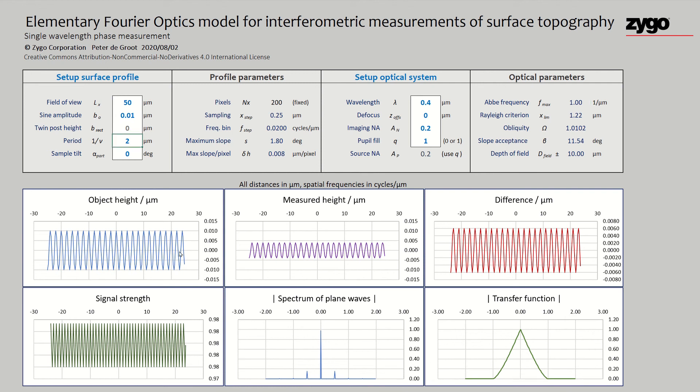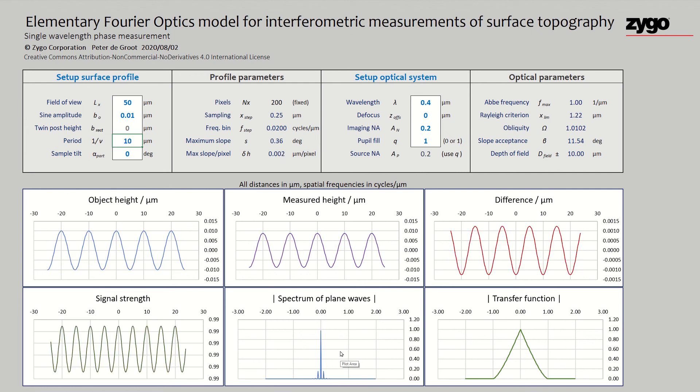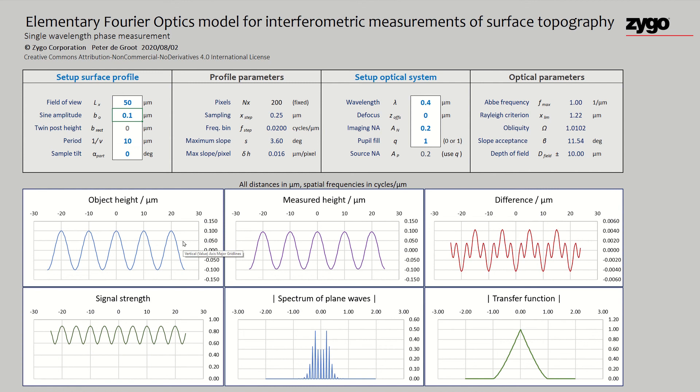If we change this period to 1, then we now have gotten to the edge and we don't see anything. So that's well understood. Let's go back to our original signal with the measured height now looking good. Let's change the amplitude instead of the period. We've changed now to 100 nanometers. At 100 nanometers, we've got a good strong measurement result. It looks almost identical to the original, even better than when we had the smaller amplitude.